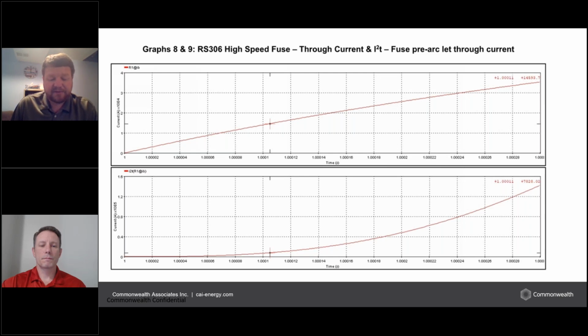And what will happen is every battery application that we worked on has been very, very unique in this regard. So even though we can calculate it for an example battery here, we'll build another battery in another location with slightly different specifications, maybe different batteries. The site specifics of where the transformer is in relation to the inverter and the battery containers is all relevant. So it needs to be modeled specifically every time. What we can do is model that in a program called EMTP-RV. This is a transient program that can model the LRC of the circuit, take into account all those factors.